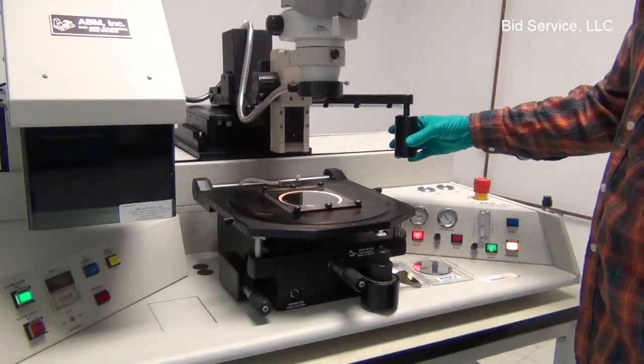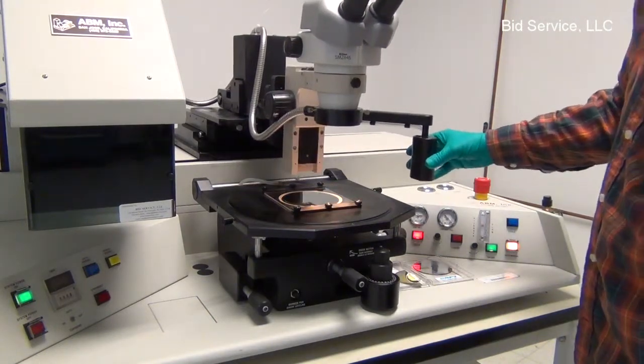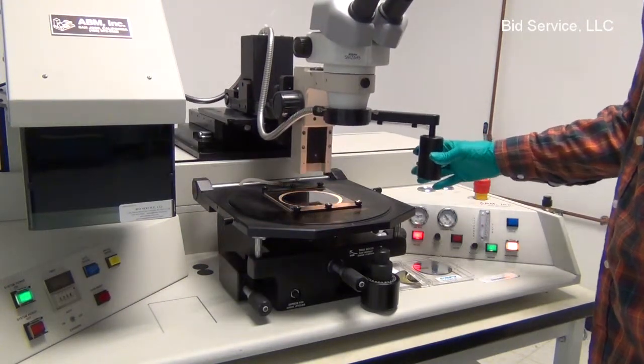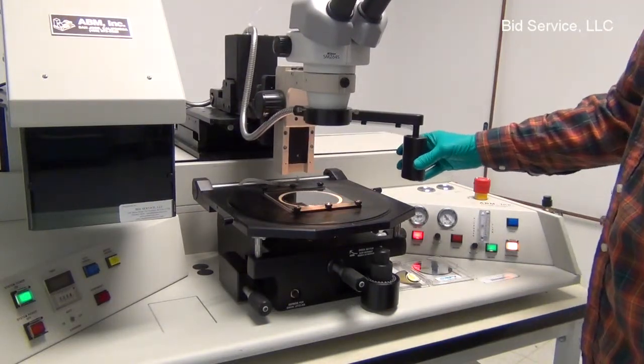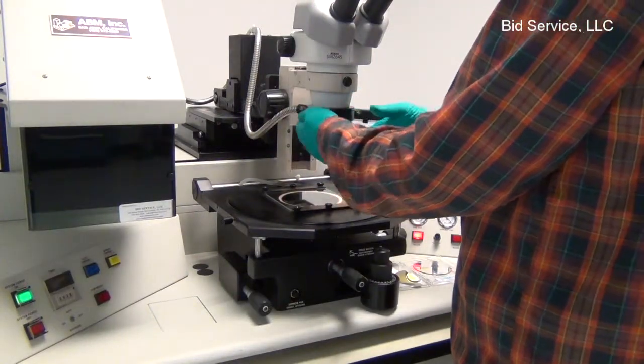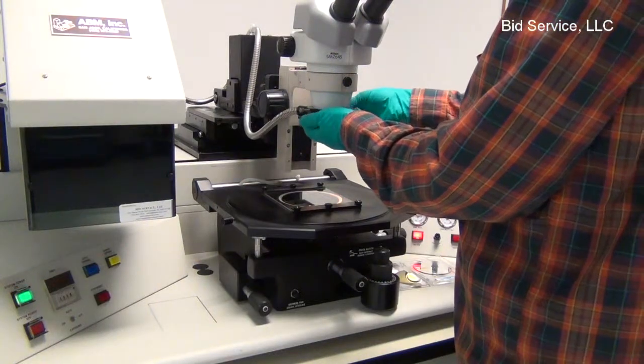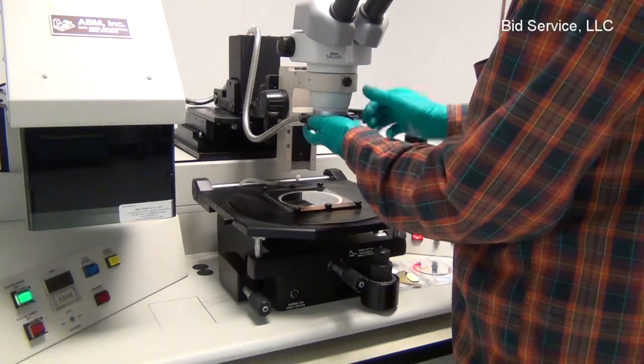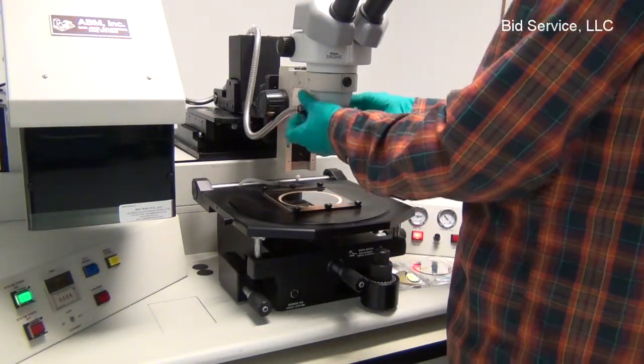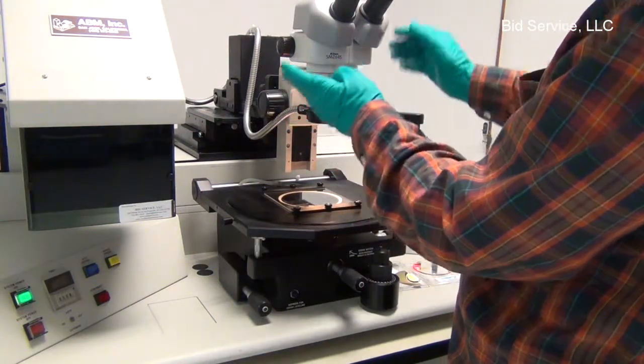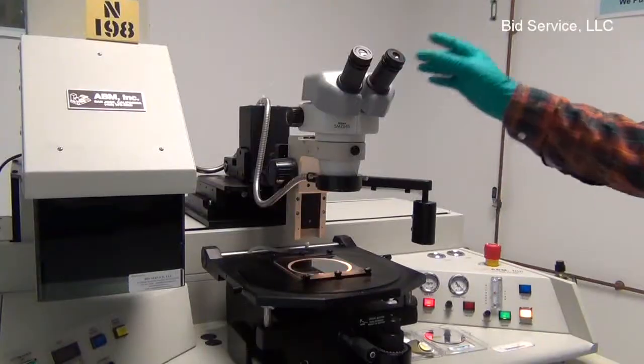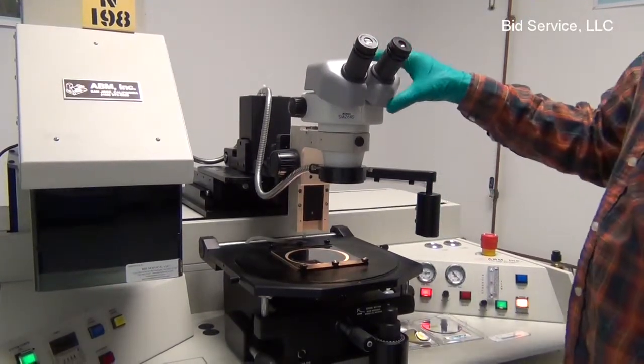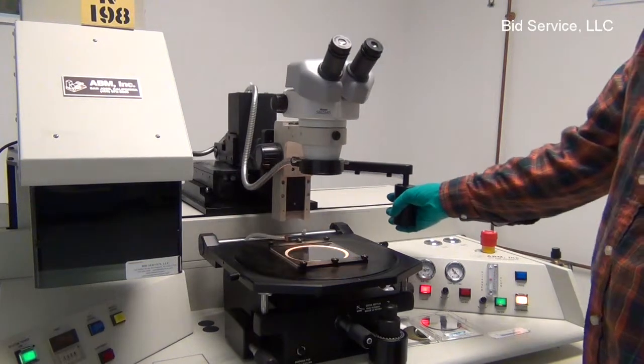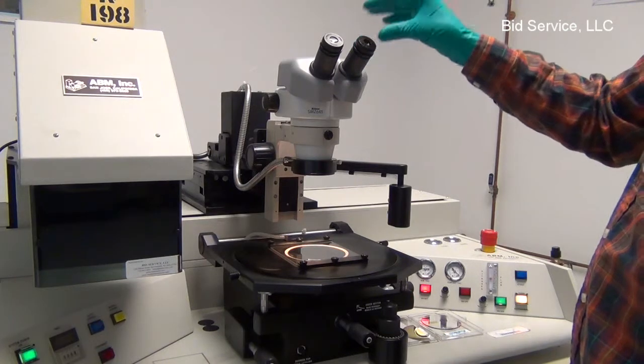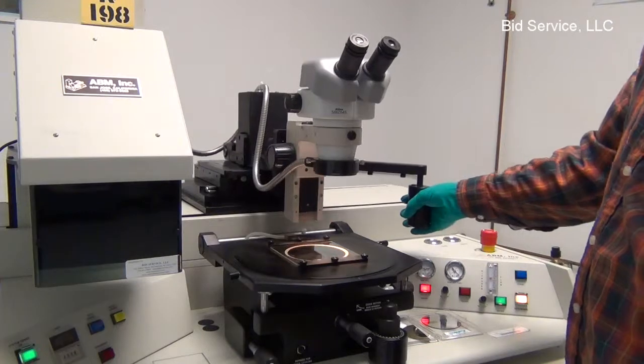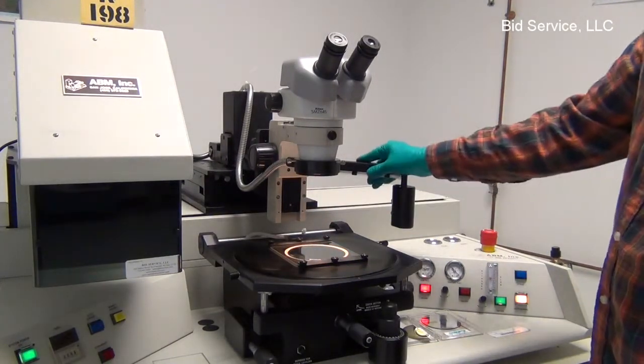There are 2 buttons on this microscope manipulator arm. By pressing them, you can move the table in X and Y directions. A fiber optic illuminator is used for illuminating the substrate, which helps to align the wafer. A Nikon stereo zoom microscope is provided, SMZ 645 model. The unit comes with at least 2 sets of eyepieces, 10x and 20x. And if the buttons are not pressed, the microscope cannot be moved.